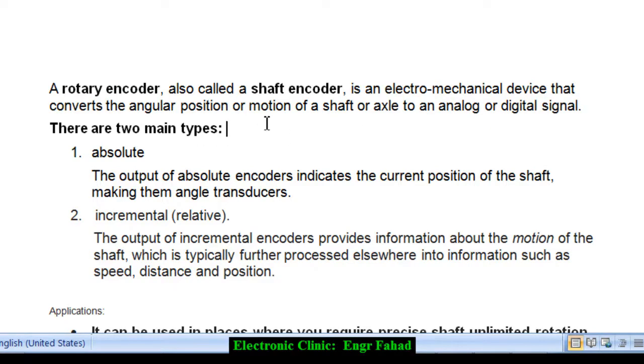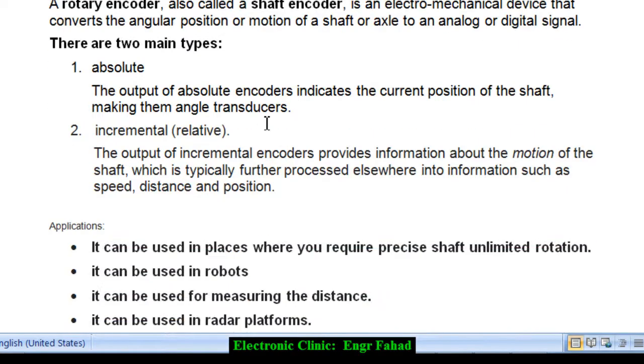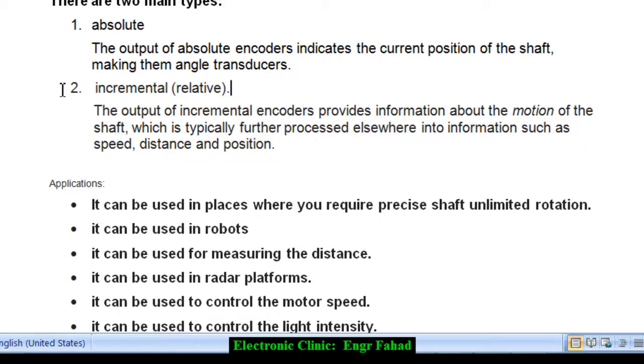There are two main types. Number one: Absolute — the output of an absolute encoder indicates the current position of the shaft, making them angle transducers. Number two: Incremental or relative — the output of incremental encoders provides information about the motion of the shaft, which is typically further processed elsewhere into information such as speed, distance, and position.